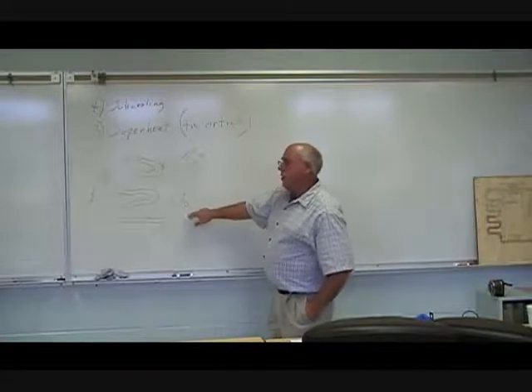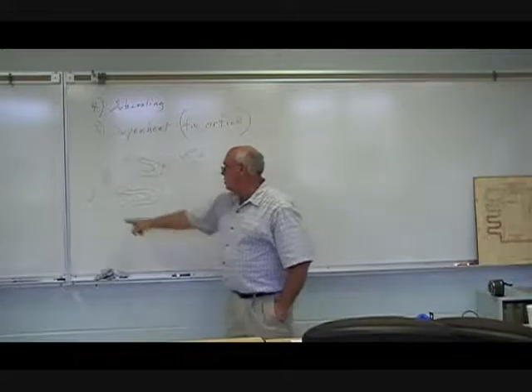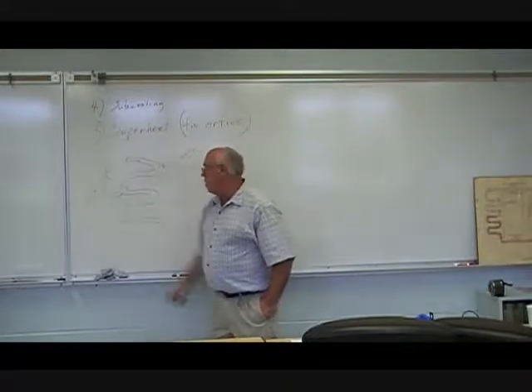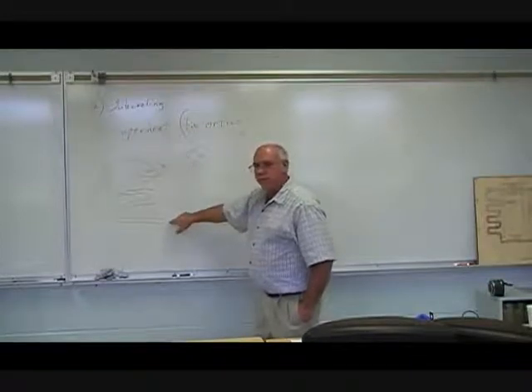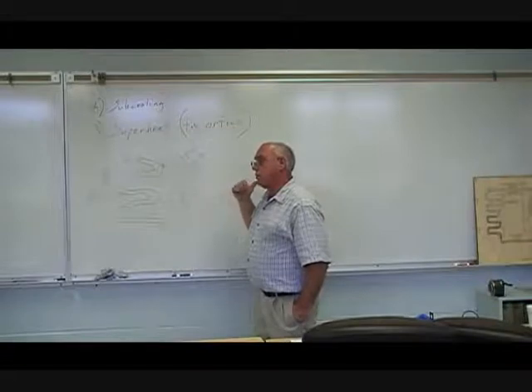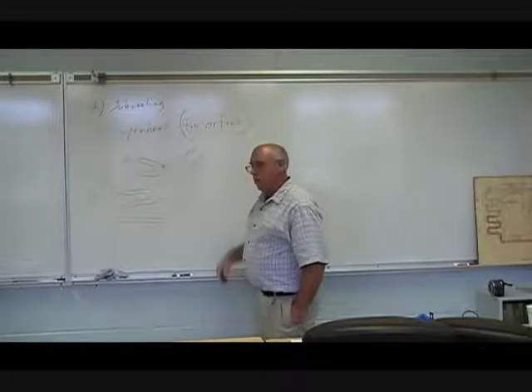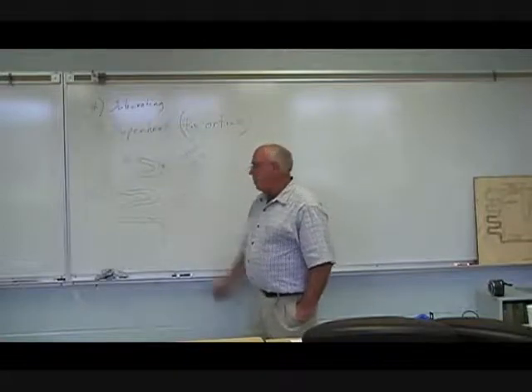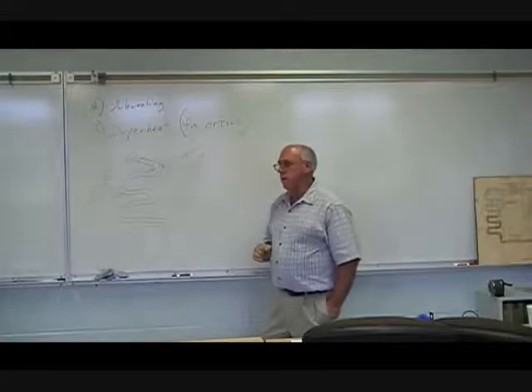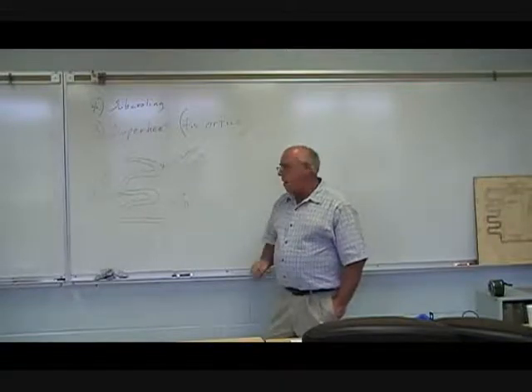So how do we figure that? We take our pressure, we go to our temperature and pressure conversion chart, we figure out what the temperature says it is at boiling, which would be 40 degrees for R22. We take the line, the evaporator line, or in this case we would say we were at the condensing unit, the suction line at the condensing unit, take that temperature. We compare that temperature with our saturation temperature. The difference is the superheat. Does that make sense?